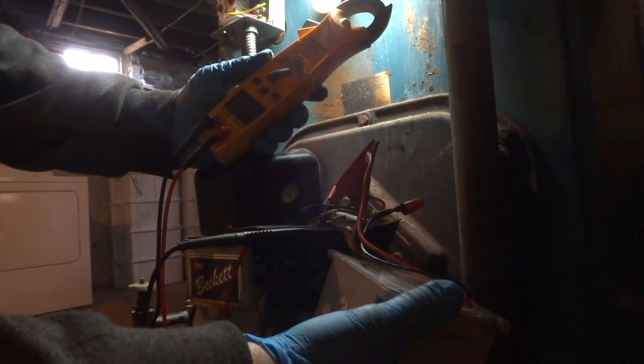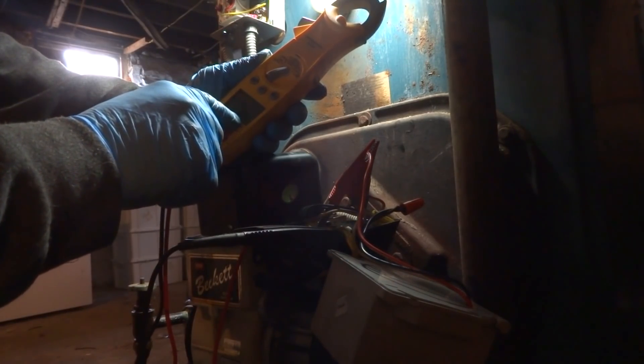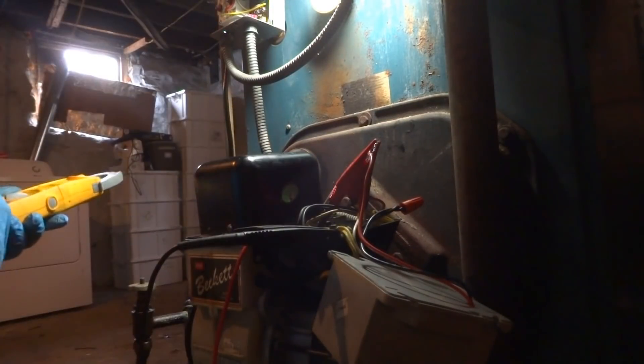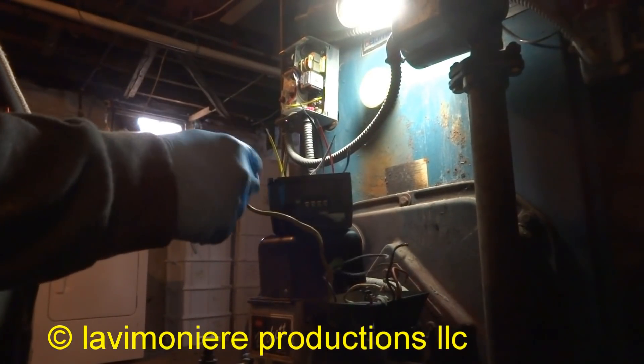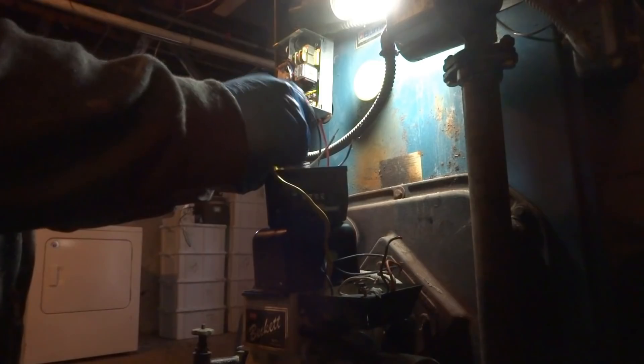What we'll do is disconnect the orange wire — it should feed the motor — and we'll see if we get it to act up. I know it's not the cad cell because I just changed that. I think it's this control that's bad. No power — I got the button pushed in. So control's bad. I've got no power, the button's pushed in — we're gonna replace that bad control. We're gonna change this control. Got the two FF terminals to hook up, which is the cad cell. Alright, that should do it.